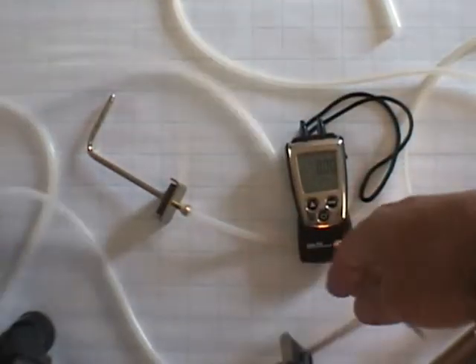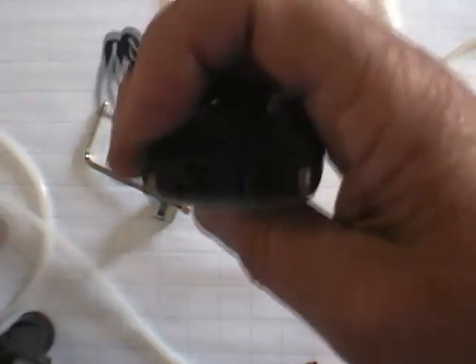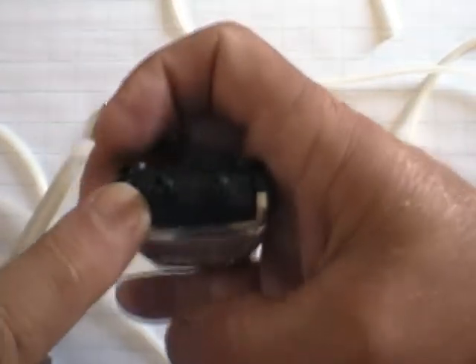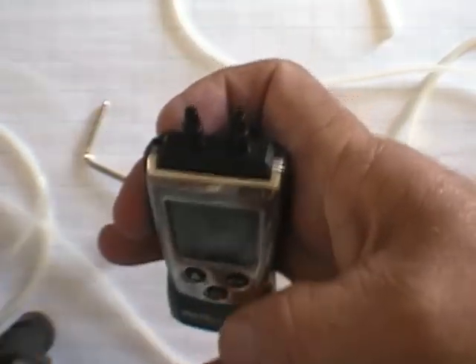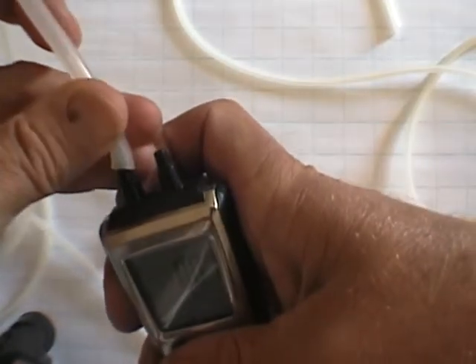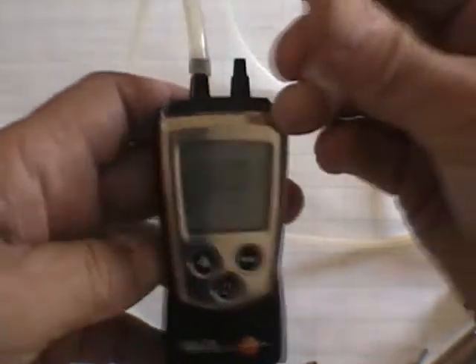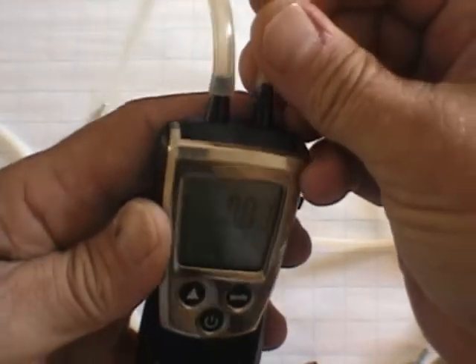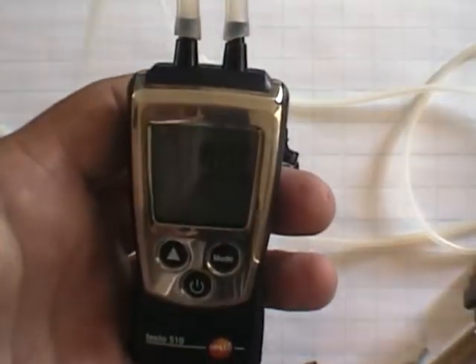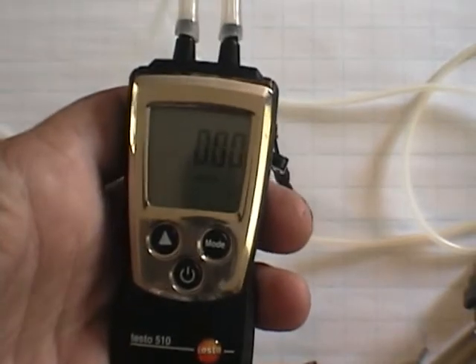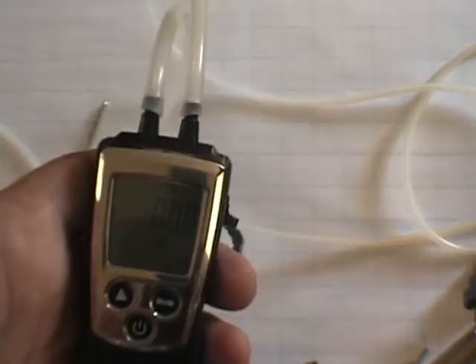Attached to that is a vinyl tube, and that vinyl tube, when we take our measurement, is going to attach either to the positive barb or the negative barb. So we can take a single pressure, or we can use two of these probes and attach it and take a total pressure, total negative and positive. It will add them together and give us a total pressure.